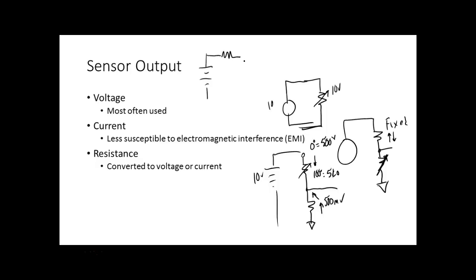So you can take a car battery, you can take an old headlight, and you can put your voltmeter across that battery, hook a headlight on it, and the voltage would drop. Well, where's the voltage dropping at? You're measuring at the battery, right? So what's dropping the voltage? Well, that's the internal resistance of the battery. Now, on generators, we have a regulator that if the output voltage tries to drop, the regulator puts more energy in the source to cause the output voltage to go back up. So regulators compensate for the internal resistance of your alternator.